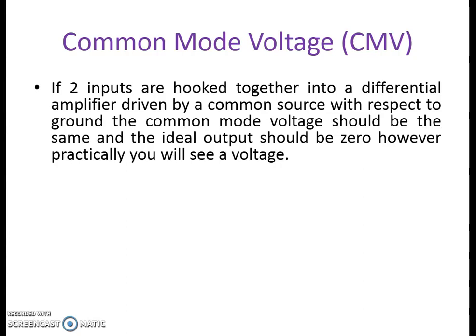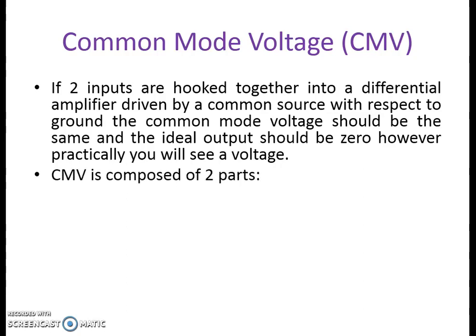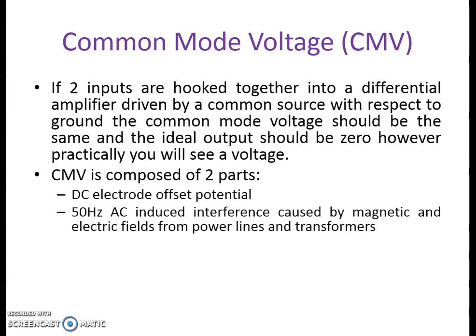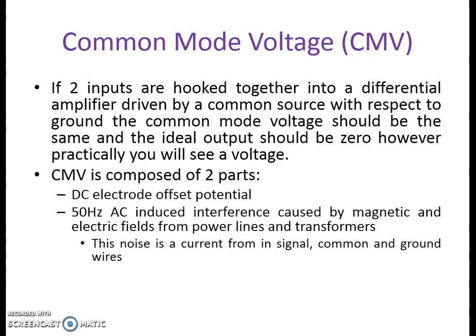If two inputs are hooked together into the differential amplifier driven by a common source, the common mode voltage should be the same and the ideal output should be zero. However, practically there is something called offset. That common mode voltage is composed of two parts: in the case of ECG, it contains a DC electrode offset potential and a 50 Hz AC-induced power line interference caused by the magnetic and electric fields from the power lines. This noise is a current formed in the signal, common, and ground wires, and is generally capacitively coupled into the circuit.